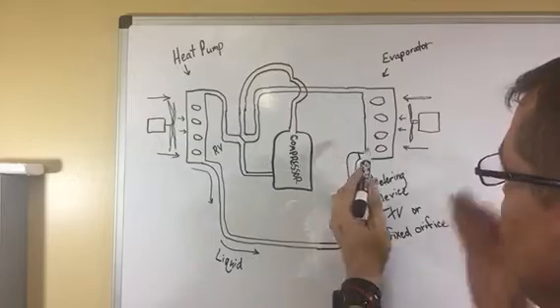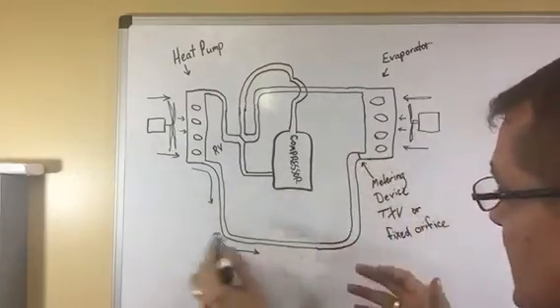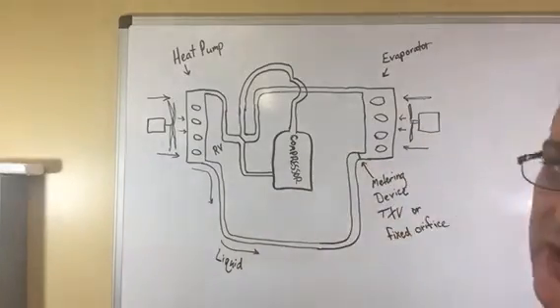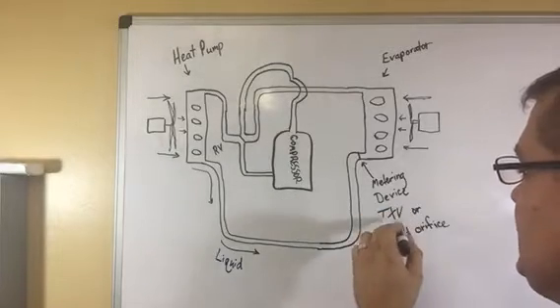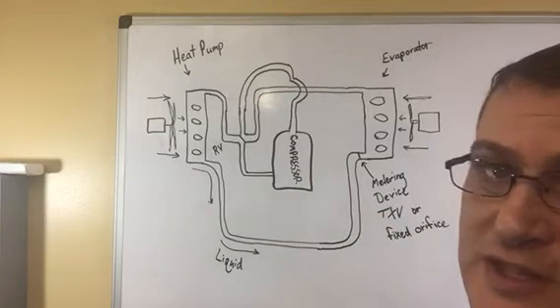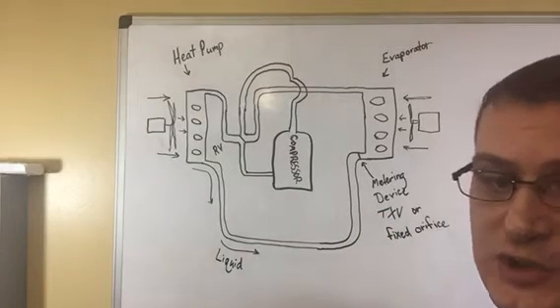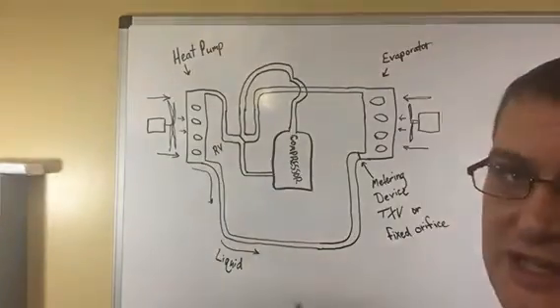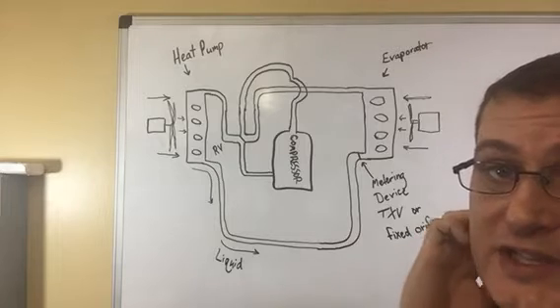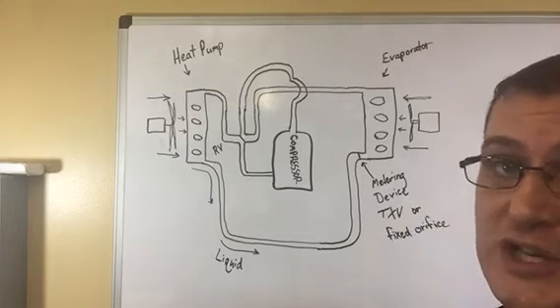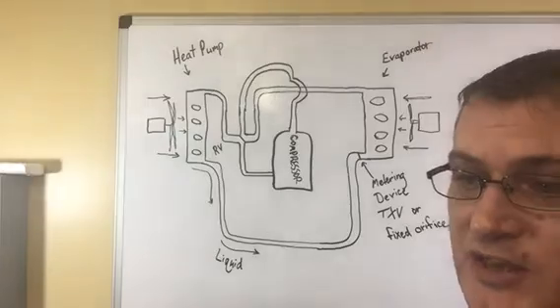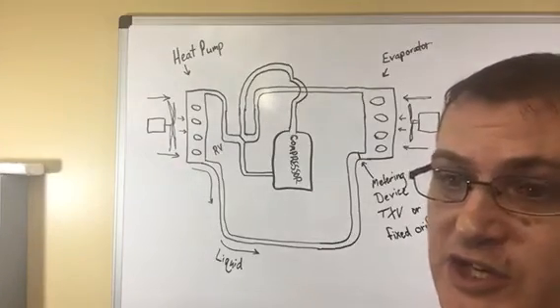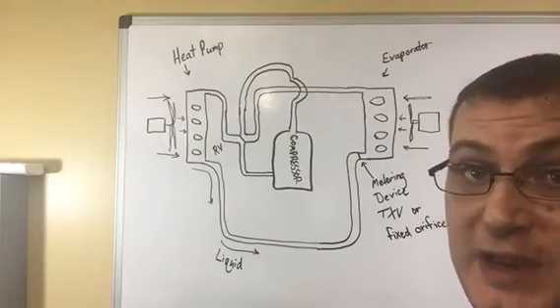It comes through to the indoor coil as a liquid where it hits a metering device. Now that metering device can be a TXV or a fixed orifice. TXV is just short for a thermostatic expansion valve. Fixed orifice is just exactly what it is. It's just a little orifice that maintains the same pressure no matter what. An expansion valve adjusts the pressure according to the demand.